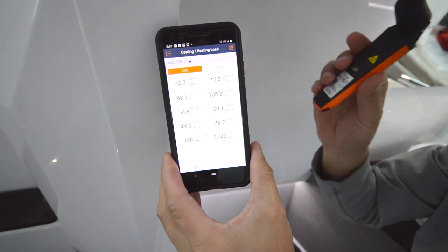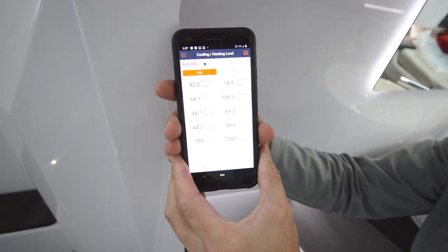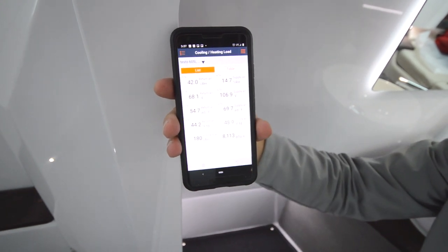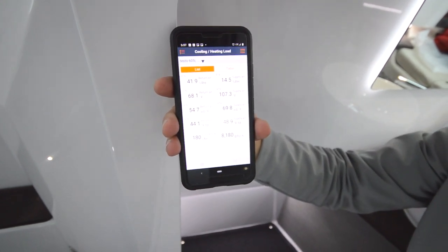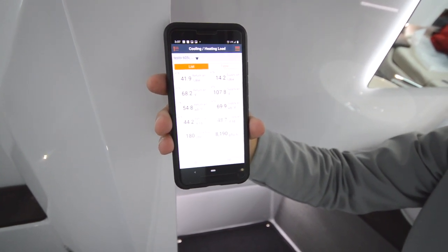Then I take the second temperature and humidity sensor and place it in the supply air grill. We'll see as that warms up the supply air temperature come up — we're over 100 degrees Fahrenheit coming out of just the 7000 BTU unit, with 68 degrees going into it.